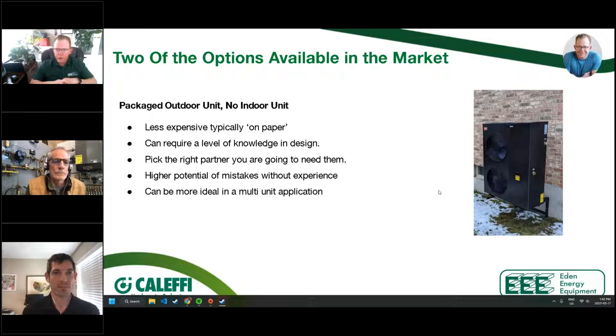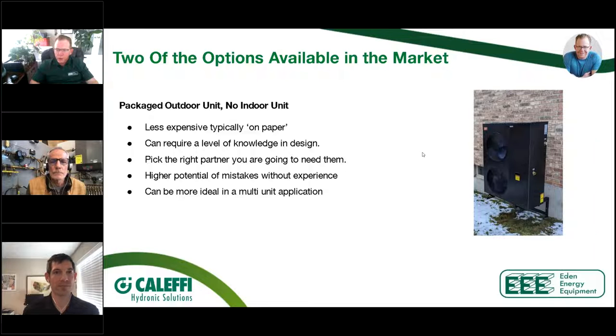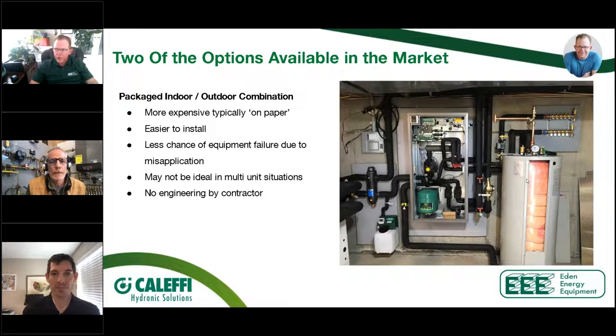Just understand that, again, we don't want to try to pigeonhole this into the application. We need to design to make sure the heat pump will, in fact, fit that application. The other option that you have is what's called a packaged indoor-outdoor unit. So this comes in a 3-ton and a 5-ton unit. This is called the Advantage unit. The outdoor unit I'm not showing here because it looks quite similar to the IBC one that you just saw. The difference between these two units is it has a fully packaged indoor unit.